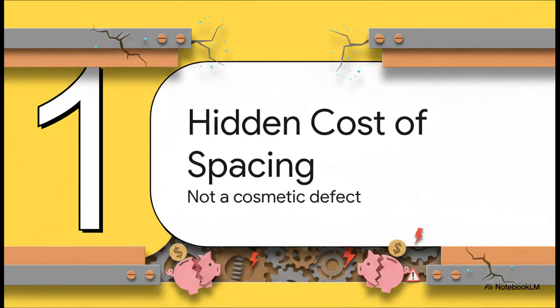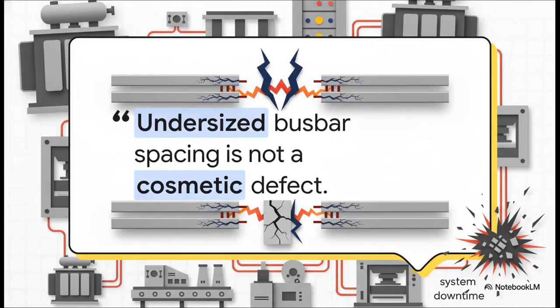Starting us off, Section 1, the hidden cost of spacing. Okay, let's dive into this. I really want to emphasize right off the bat that busbar spacing is definitely not some minor cosmetic detail you just handle at the very end of your build. The source material makes this incredibly clear. Undersized spacing is a direct path to arc ignition, severe insulation tracking, and dielectric failure. Basically, treating it as an afterthought is a recipe for a catastrophic meltdown and entirely avoidable downtime on the factory floor. It's a huge deal.